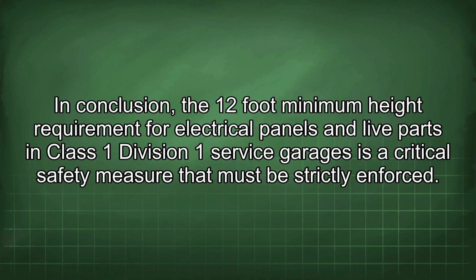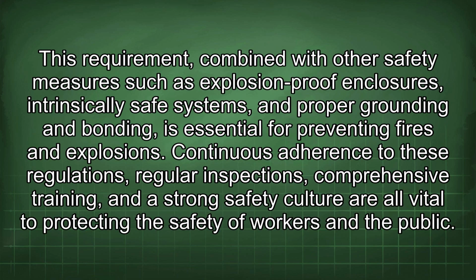In conclusion, the 12-foot minimum height requirement for electrical panels and live parts in Class 1 Division 1 service garages is a critical safety measure that must be strictly enforced. This requirement, combined with other safety measures such as explosion-proof enclosures, intrinsically safe systems, and proper grounding and bonding, is essential for preventing fires and explosions. Continuous adherence to these regulations, regular inspections, comprehensive training, and a strong safety culture are all vital to protecting the safety of workers and the public.